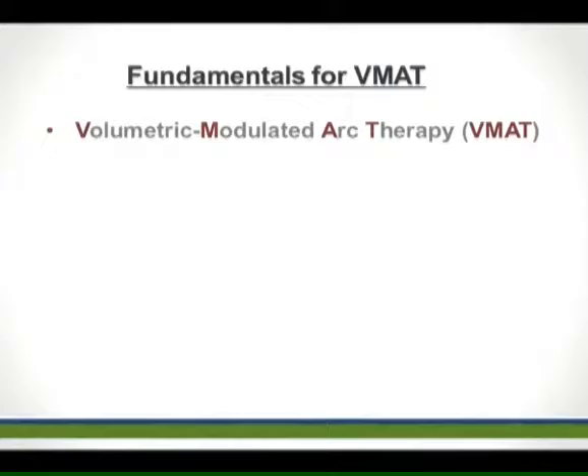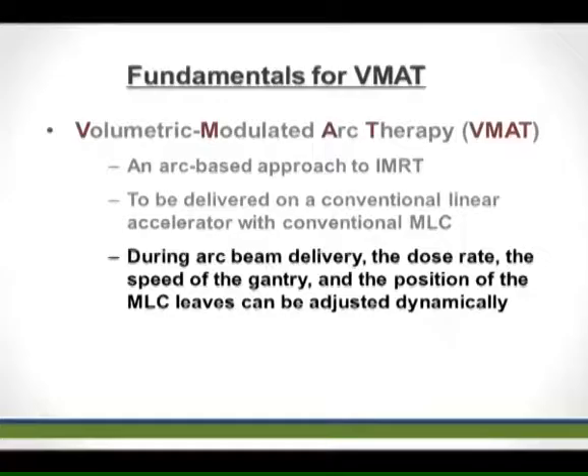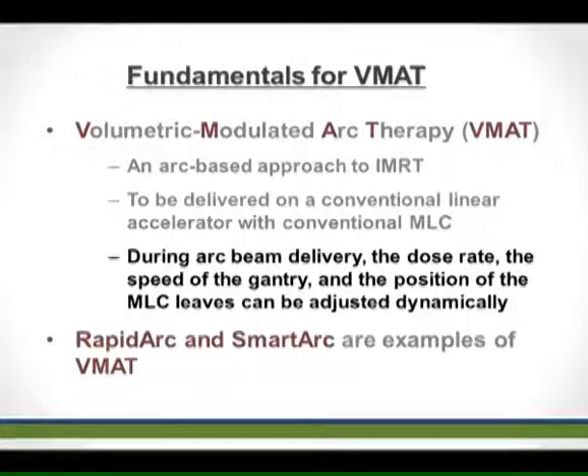Volumetric modulated arc therapy is just one form of IMRT, although with a rotational flavor. It can usually be delivered using a conventional linear accelerator with conventional MLC. The characteristics of VMAT include many changing parameters during dose delivery, such as dose rate, gantry speed, and the speed of MLC leaves. Examples from different vendors include RapidArc and SmartArc.